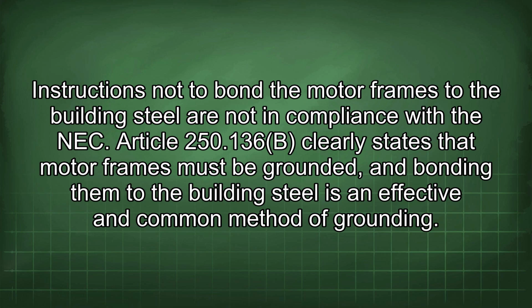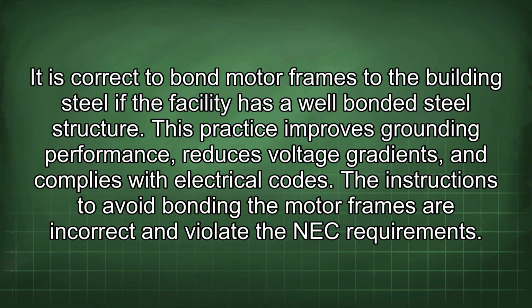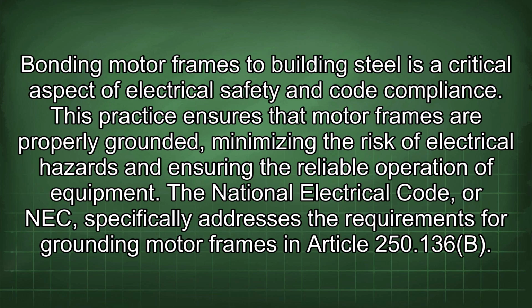Article 250.136(B) clearly states that motor frames must be grounded, and bonding them to the building steel is an effective and common method of grounding. It is correct to bond motor frames to the building steel if the facility has a well-bonded steel structure. This practice improves grounding performance, reduces voltage gradients, and complies with electrical codes. The instructions to avoid bonding the motor frames are incorrect and violate the NEC requirements. Bonding motor frames to building steel is a critical aspect of electrical safety and code compliance.